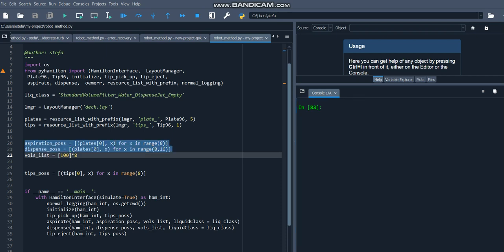Now let's declare a pair of aspiration and dispense lists. These work similarly to sequences from Venus, but instead of declaring references to static objects in a lay file, we declare these on the fly, usually using a list comprehension, because list comprehensions are very convenient ways of specifying liquid handling patterns. In this case, we'll be aspirating from the first column of the plate, and then dispensing to the second column of the plate.